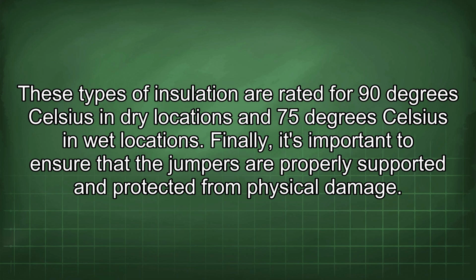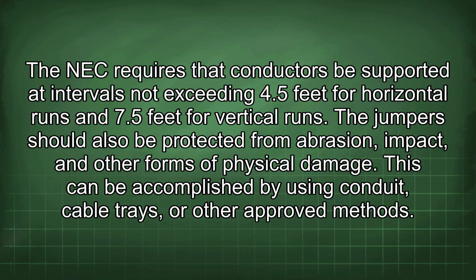Finally, it's important to ensure that the jumpers are properly supported and protected from physical damage. The NEC requires that conductors be supported at intervals not exceeding 4.5 feet for horizontal runs and 7.5 feet for vertical runs. The jumpers should also be protected from abrasion, impact, and other forms of physical damage. This can be accomplished by using conduit, cable trays, or other approved methods.